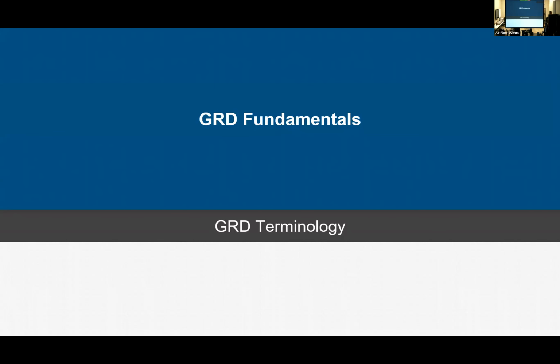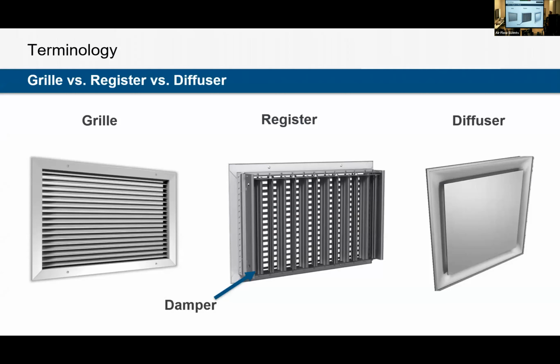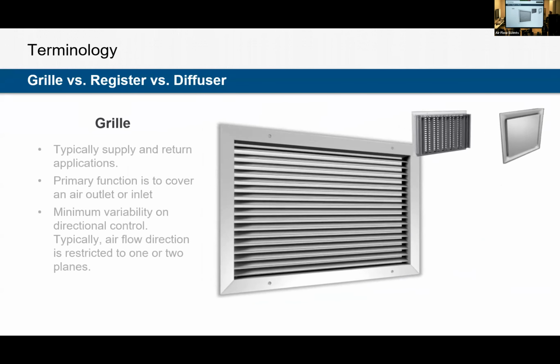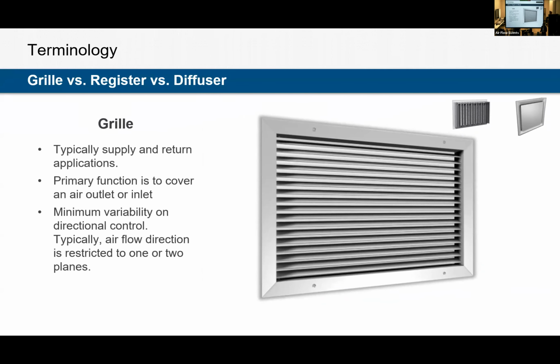Okay, that's a mixed system. Jump into GRD specifically in some of the terminology. So GRD stands for grill, register, and diffuser. These are pretty much 3 different types of air outlets. The first one here being a grill. Your grill is your simplest. It's really just a hole cover, essentially. Very little variability in the discharge of a grill. Usually you're only discharging air in 1 or 2 planes. But very versatile as far as sizing goes.